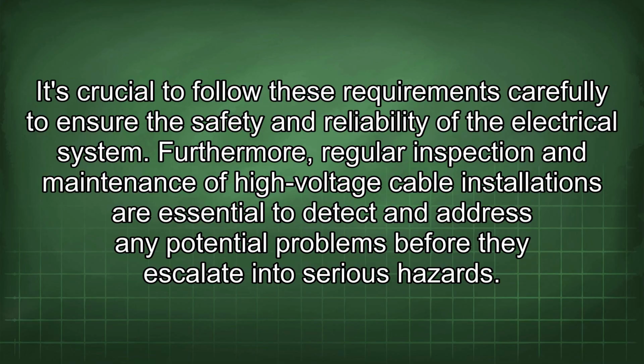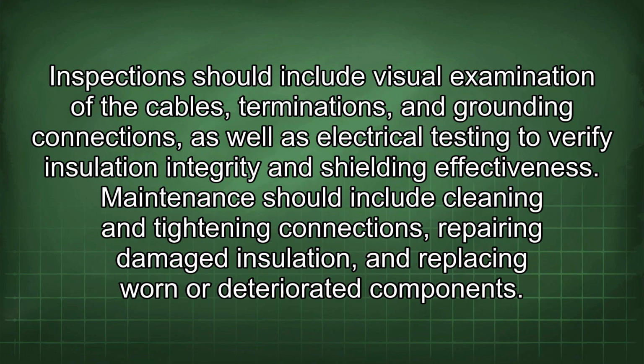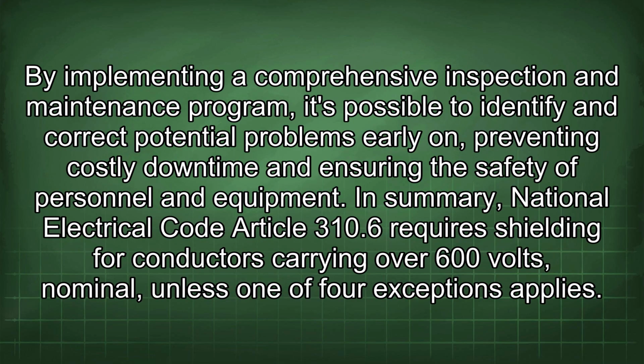Furthermore, regular inspection and maintenance of high-voltage cable installations are essential to detect and address any potential problems before they escalate into serious hazards. Inspection should include visual examination of the cables, terminations, and grounding connections, as well as electrical testing to verify insulation integrity and shielding effectiveness. Maintenance should include cleaning and tightening connections, repairing damaged insulation, and replacing worn or deteriorated components. By implementing a comprehensive inspection and maintenance program, it's possible to identify and correct potential problems early on, preventing costly downtime and ensuring the safety of personnel and equipment.